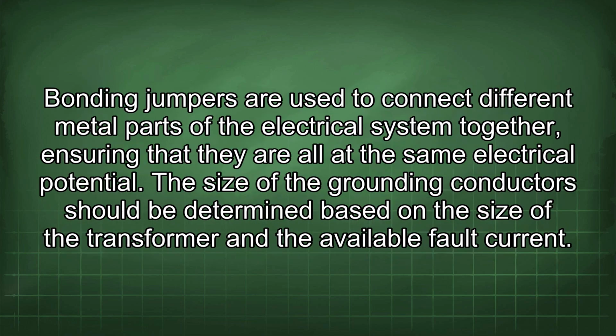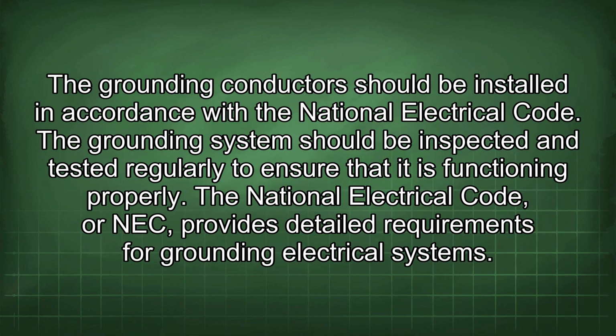Bonding jumpers are used to connect different metal parts of the electrical system together, ensuring that they are all at the same electrical potential. The size of the grounding conductor should be determined based on the size of the transformer and the available fault current. The grounding conductor should be installed in accordance with the National Electrical Code. The grounding system should be inspected and tested regularly to ensure that it is functioning properly.